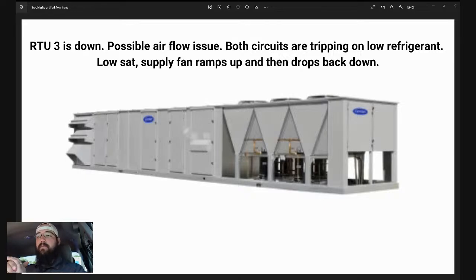So the technician gets there and he's looking into it. He sees the supply fan ramp up to about 2 inches of static, and then it comes back down. Now this obviously does have a VFD in it. It was a little challenging seeing that supply fan do that and trying to understand what is happening that's causing it to spike that high on static and then come back down. He said once it ramped down, it leveled off at around 40 hertz, but if I understood him correctly, the supply fan speed was still fluctuating a little bit. At that stage he was hovering around 1 inch.